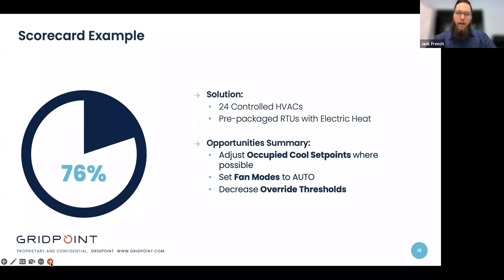Okay, so the takeaway from the scorecard might look like this. As I mentioned, the solution was an auto dealership with 24 controlled HVACs. They were prepackaged RTUs with electric heat. So what were our opportunities? The biggest one, with 3 points in opportunity score, was the occupied cool set point. So wherever possible, increase the occupied cooling set points. If we can get to an average of 73 degrees, up from 72, then we'll have 3 points instead of only 2 points for that category. And that'll improve our overall score of 76% even further past the vertical benchmark.